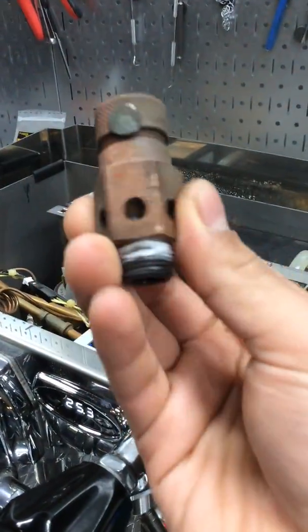We also had to replace the boiler safety valve. As you can see, this one is very corroded and it was actually leaking steam through here. So this is the one that we just replaced.